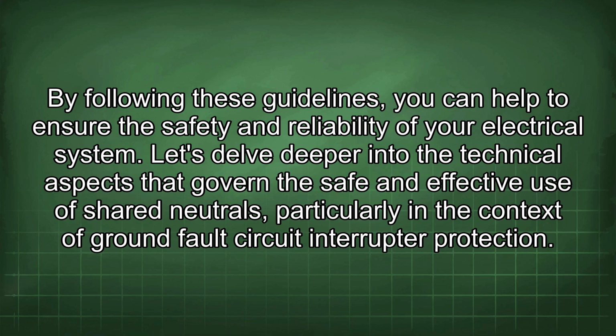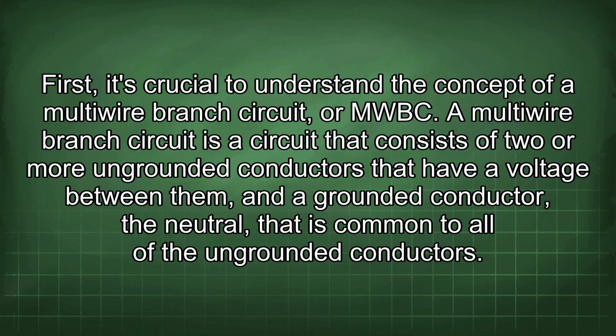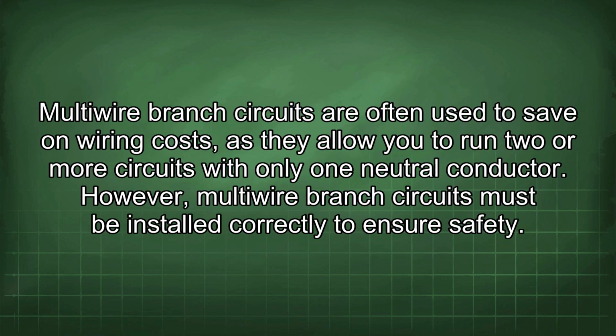Let's delve deeper into the technical aspects that govern the safe and effective use of shared neutrals, particularly in the context of ground fault circuit interrupter protection. First, it's crucial to understand the concept of a multi-wire branch circuit, or MWBC. A multi-wire branch circuit is a circuit that consists of two or more ungrounded conductors that have a voltage between them and a grounded conductor, the neutral, that is common to all of the ungrounded conductors. Multi-wire branch circuits are often used to save on wiring costs, as they allow you to run two or more circuits with only one neutral conductor.